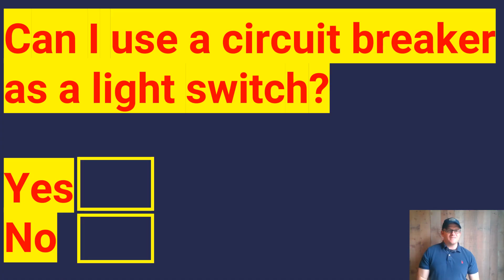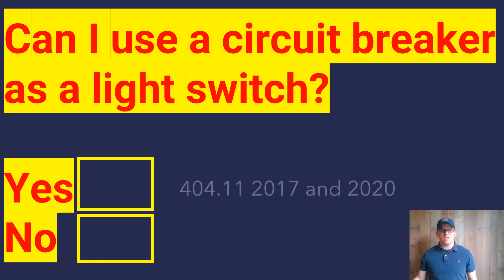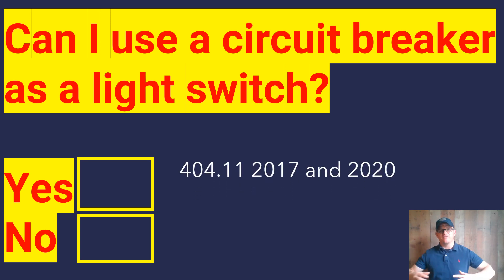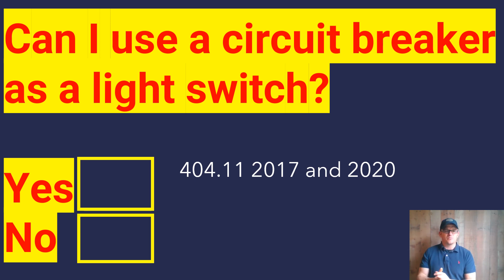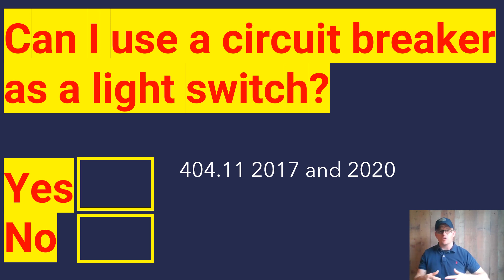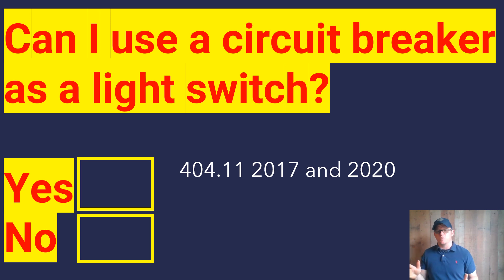All right, guys, so the question that we're looking at today is: can I use a circuit breaker as a light switch? And the short answer is yes, you can. We're going to find this in 404.11 in the 2017 and in the 2020. You can use a circuit breaker as a light switch as long as it has the required number of poles on that circuit breaker, but you're also going to have to watch out for readily accessible location and all of the other things that go along with overcurrent devices and as well with switches.